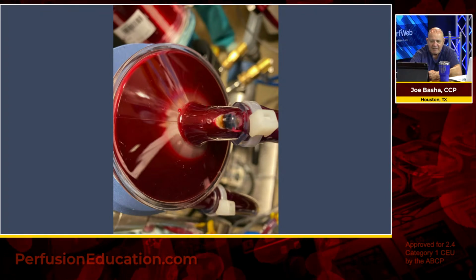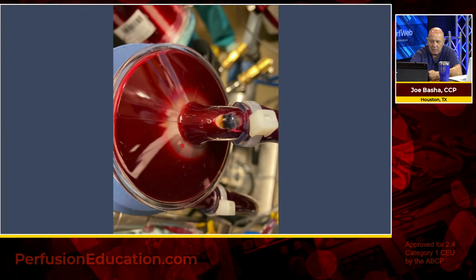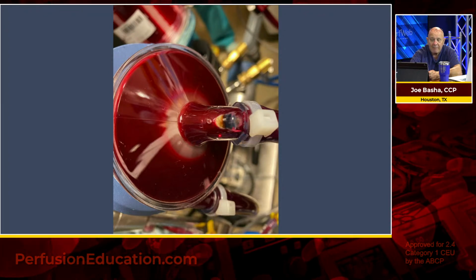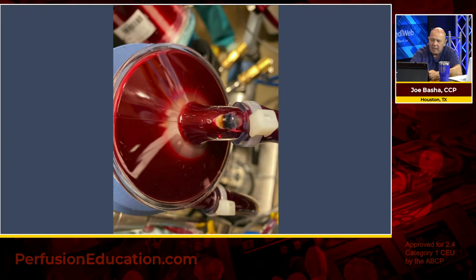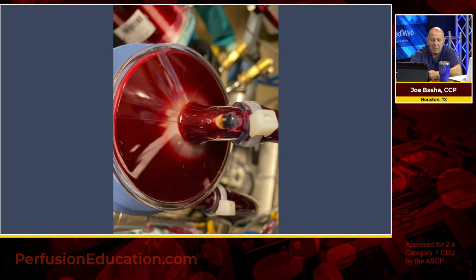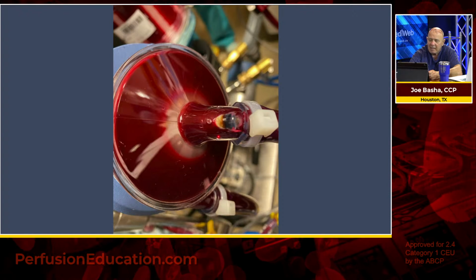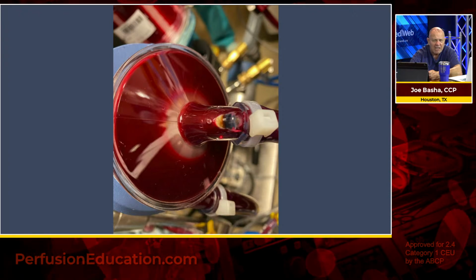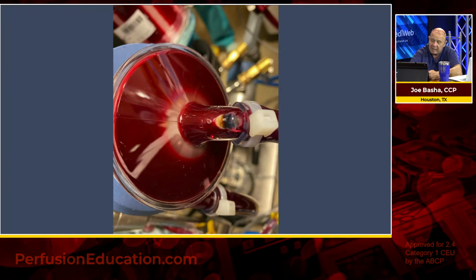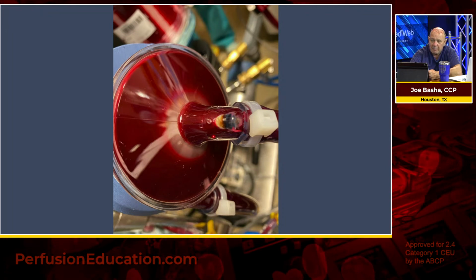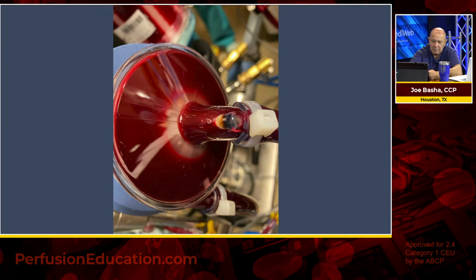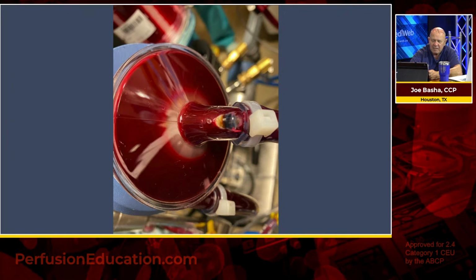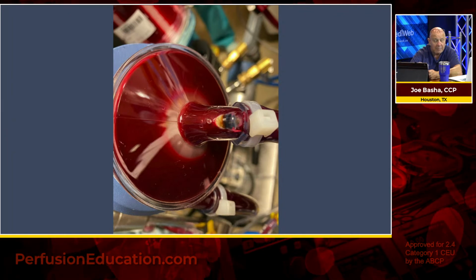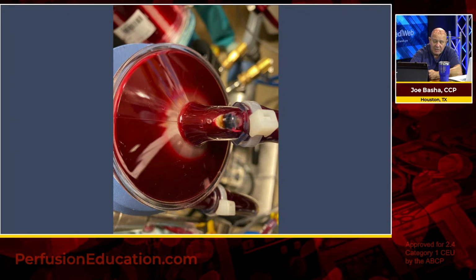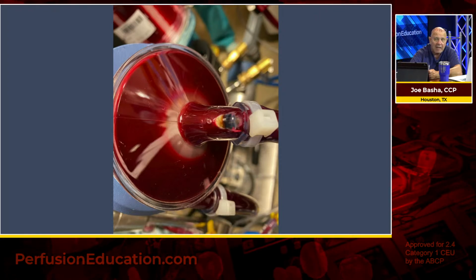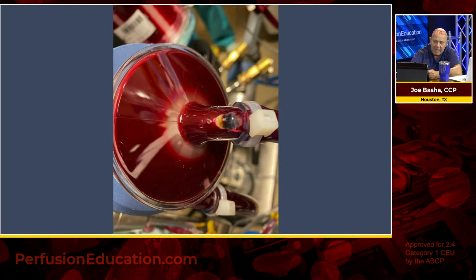This is cavitation. And so this had to be changed, obviously emergently, but the patient was doing pretty well, thankfully, and tolerated the change pretty well. Now, he didn't like it, but the patient had enough reserve to tolerate all of what happened, but it happened very acutely. And actually, the first indication was a very loud noise of this pump head.